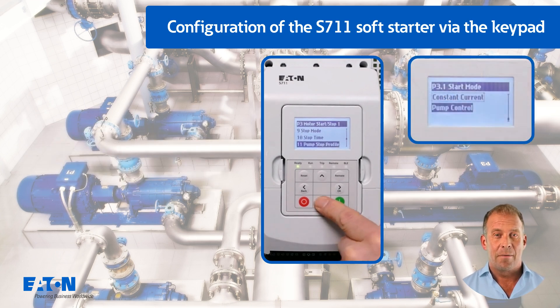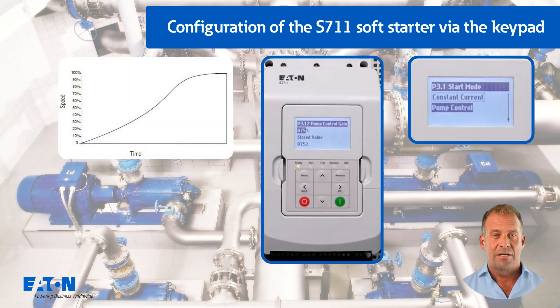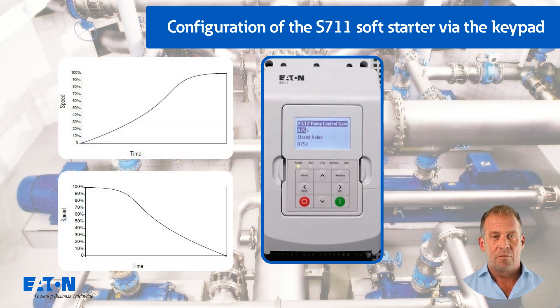With the start mode set to pump control, the S711 provides a very interesting feature for optimised starting and stopping of a pump. If the pump does not perform this properly, fine tuning can be carried out using parameter P3.12 pump control gain.